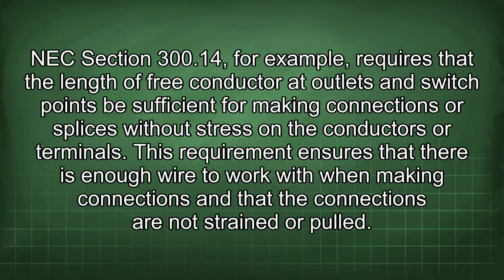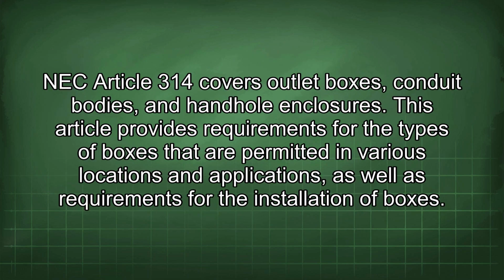NEC Section 300.14, for example, requires that the length of free conductor at outlets and switch points be sufficient for making connections or splices without stress on the conductors or terminals. This requirement ensures that there is enough wire to work with when making connections and that the connections are not strained or pulled. NEC Article 314 covers outlet boxes, conduit bodies, and handhole enclosures.